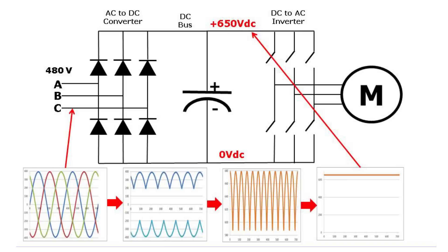If you look at the schematic in front of you, you will see three arrow-looking devices on the left. These arrow-looking devices in the electrical world are called diodes. In the mechanical or plumbing world, we might think of these as check valves — they basically let current flow in only one direction, that is the direction of the arrows. So we have an AC-to-DC converter, or just 'converter' for short, which converts the three-phase AC power to DC.